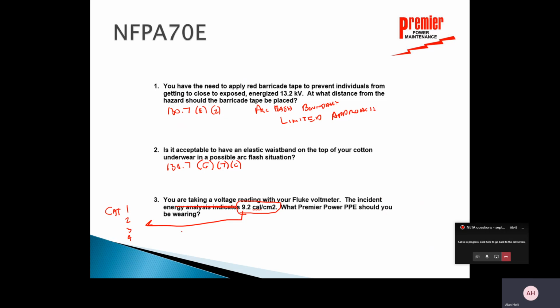So we need to understand that our clothing is basically 8 calories. If you don't look at the label, you just take the clothing that you order off of Tyndall, and that's the old category 2. That's going to be good for at least 8 calories. So what should we be wearing as Premier Power employees? This incident energy exceeds our 8-calorie shirt and our 8-calorie pants. Now you might get lucky and look at the shirt collar and see that it's over 8 and might meet this arrangement, but generally speaking, it exceeds our clothing. So we're going to go straight to our 40 cal arc suit, because our basic concept is below 8 or above 8. If it's below or equal to 8, our work clothes are great. Above 8, it's a 40 cal arc suit unless it exceeds that 40 cals. So we're going to have that 40 cal arc suit on.